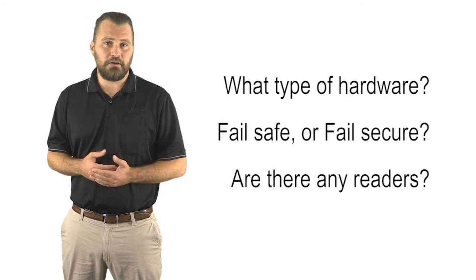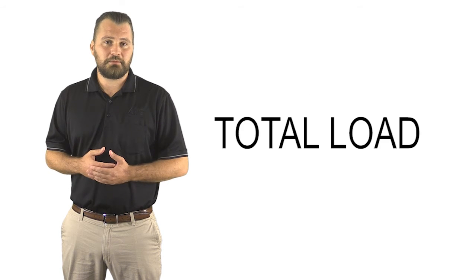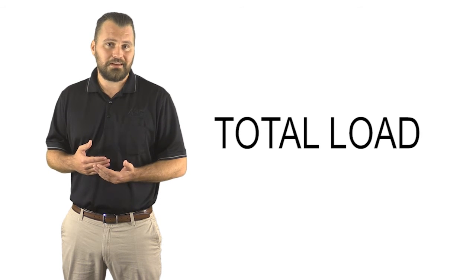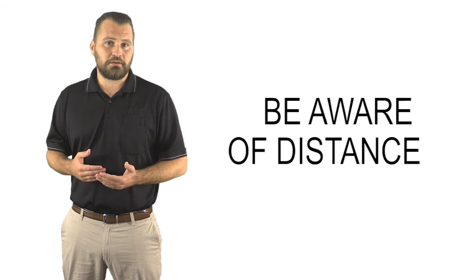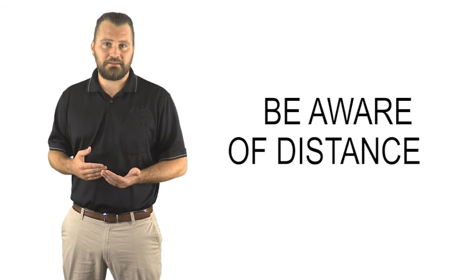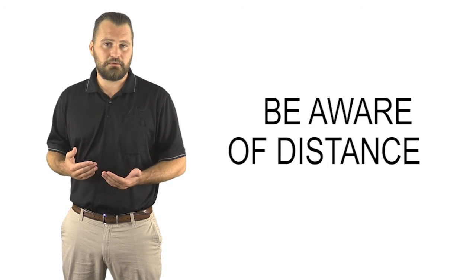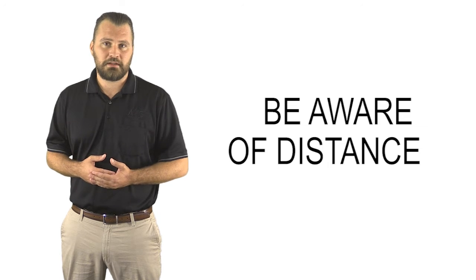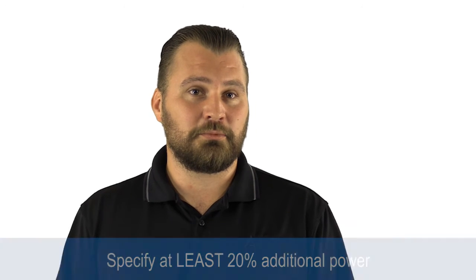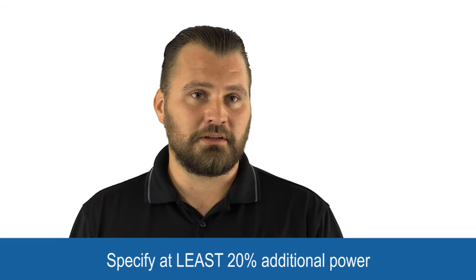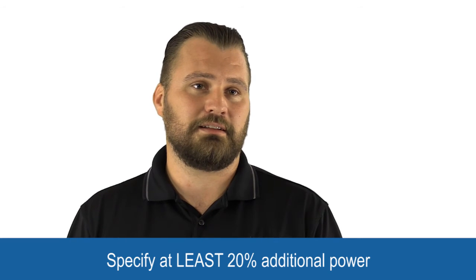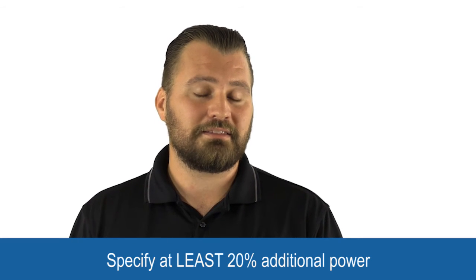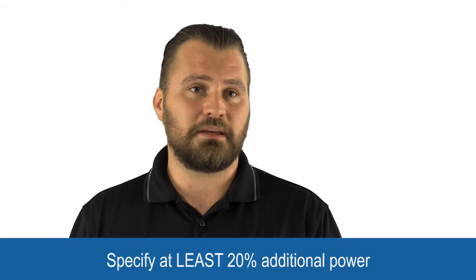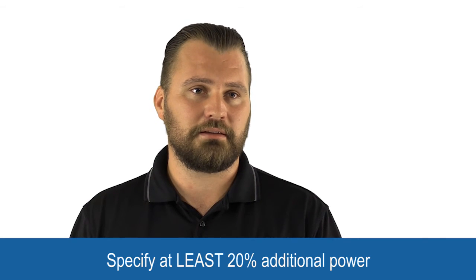Once you've identified all the powered devices, you can calculate the total load. The total number of devices also helps you choose which distribution board you need to power all the devices. You also need to be aware of the distance the power supply is from the devices it's powering, because the longer the cable, the more voltage drop can occur. The final thing to consider is that whenever you're specifying a power supply, you need to account for at least an additional 20% power. This helps protect the system, as it is never acceptable to max out any power supply.